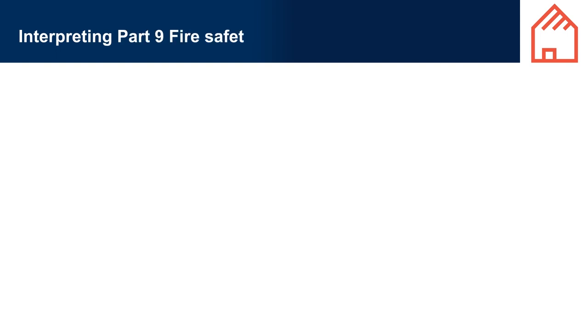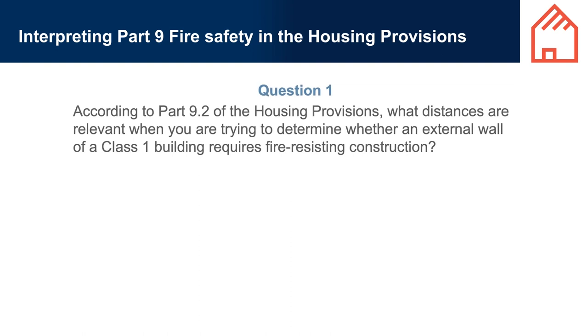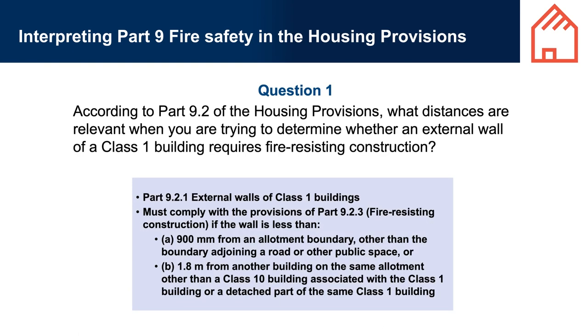Interpreting Part 9 Fire Safety in the Housing Provisions. Question 1: According to Part 9.2, what distances are relevant when determining whether an external wall of a Class 1 building requires fire-resisting construction? Answer: Part 9.2.1 states external walls of Class 1 buildings must comply with Part 9.2.3 Fire-Resisting Construction if the wall is less than (a) 900 millimetres from an allotment boundary other than one adjoining a road or public space, or (b) 1.8 metres from another building on the same allotment, other than a Class 10 building associated with the Class 1 building or a detached part of the same Class 1 building.